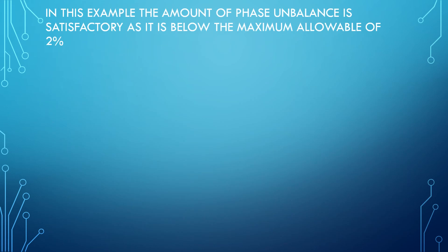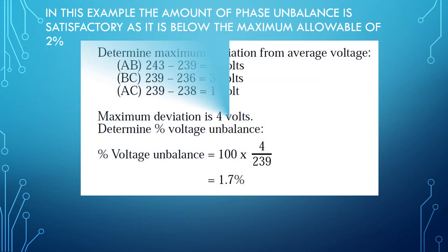In this example, the amount of phase unbalance is satisfactory, as it is below the maximum allowable of 2%. We determined the maximum deviation from average voltage was 4 volts.